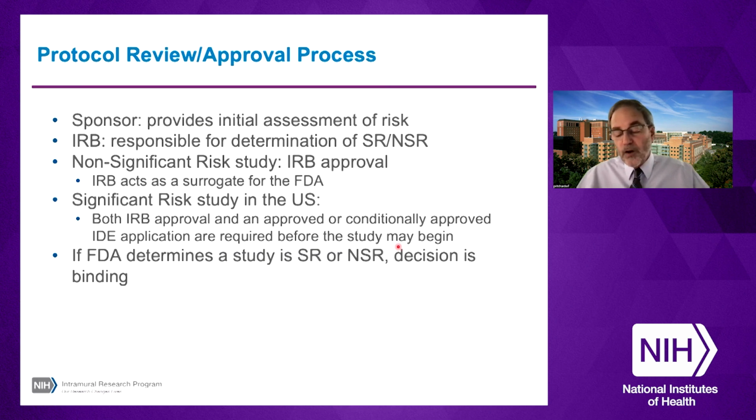You might argue that it's a non-significant risk device because, and define why that is. The IRB then will review your protocol, and they are responsible for determining whether it's a significant risk or a non-significant risk study. If the IRB determines that it is a non-significant risk study, then the IRB can go forward and simply review it and approve it as they would any other study.